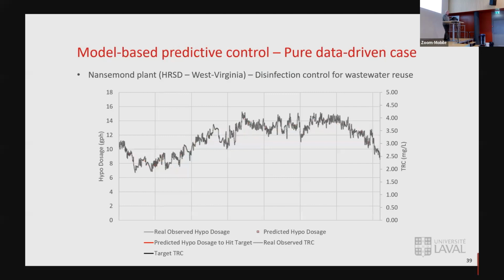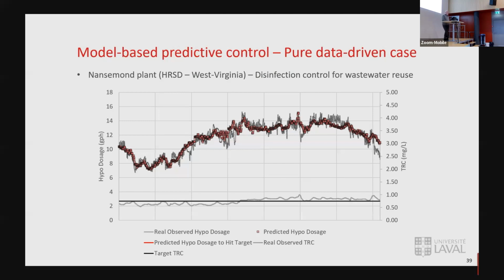And the great thing is what they did on normal operation - this is the new thing - that leads to this result in residual hypochlorite. So you obviously have the 0.5 or 0.7 milligrams per liter they want to reach. It's not optimal because it's a bit too much. You want this flat line, so they could improve and say, okay, with the model we can now use it to say what should be done optimally to reach that flat line - like optimal control. Now here it doesn't make a big difference, you don't gain money with this one.